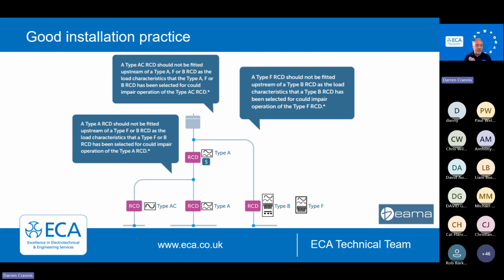The type Bs and the type Fs will look at DC. They will be able to detect a DC presence of a form or magnitude, and when it gets to a certain threshold, they will be able to disconnect that device. That's the fundamental difference. However, importantly, type Bs and type Fs are lone rangers. They do not like to be near or downstream of As and ACs. They need to be on their own. And that's important, that also the way they operate, they don't go blinding anything upstream.